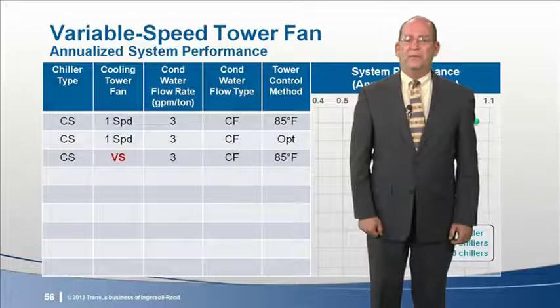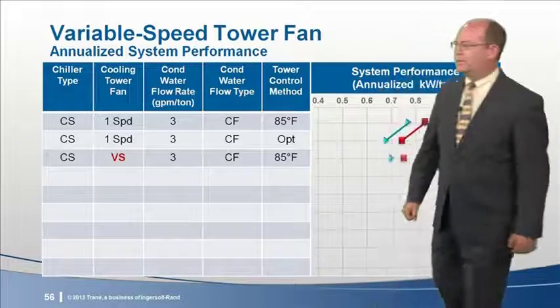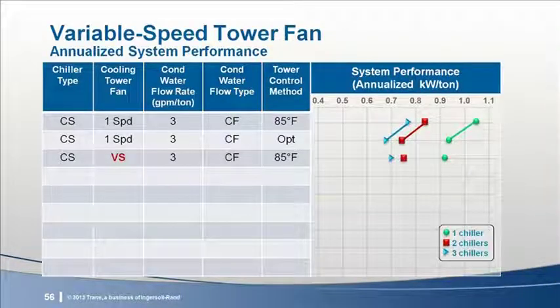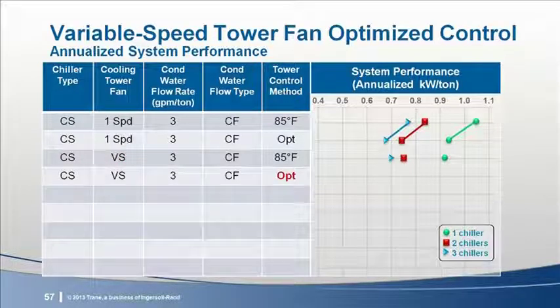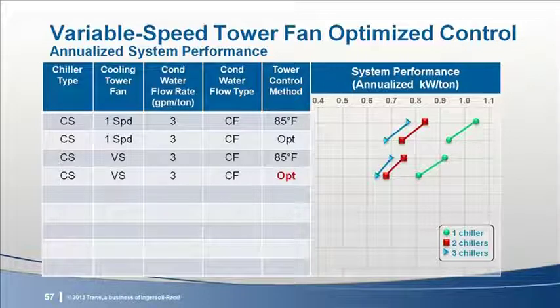The next alternative begins with the base case but applies a variable speed fan to the cooling tower. Just putting a VFD on the cooling tower fan reduced energy consumption more than applying optimal control to a fixed speed tower fan. We can see why 90.1 required tower fan speed control back in 1999. Now we'll take this same system and optimize cooling tower fan control. Again, there's a significant savings simply by dynamically finding the optimal tower set point. Frankly, performance is beginning to look pretty decent on an annualized basis.